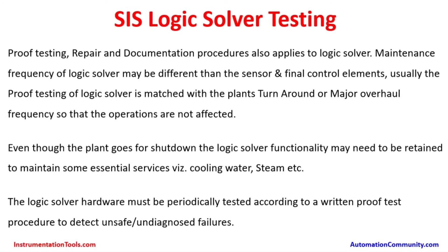Even during a short shutdown, the plant process may keep running because cooling water, instrumentation, and air requirements will still be there. It is not easy to test the logic solver even during a short shutdown — it requires proper calculation and enough resources. Only during a major turnaround, when all equipment is isolated, will the logic solver testing not have much impact on operations. The logic solver hardware must be periodically tested according to a written proof test procedure to detect unsafe and dangerous failures.